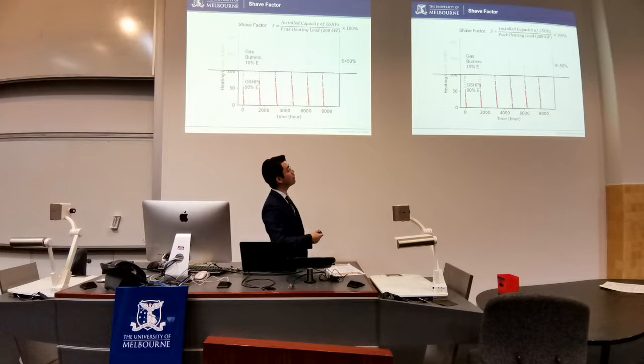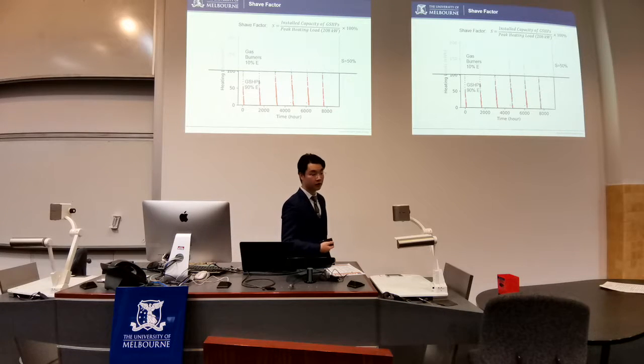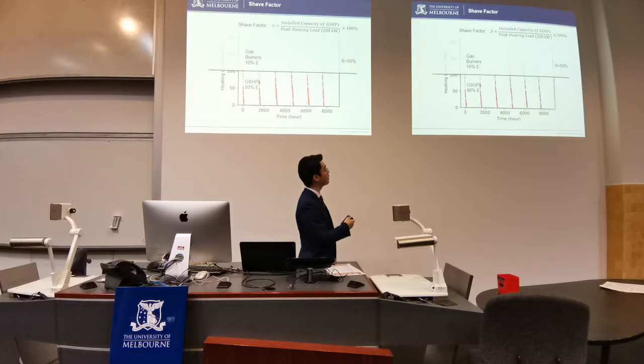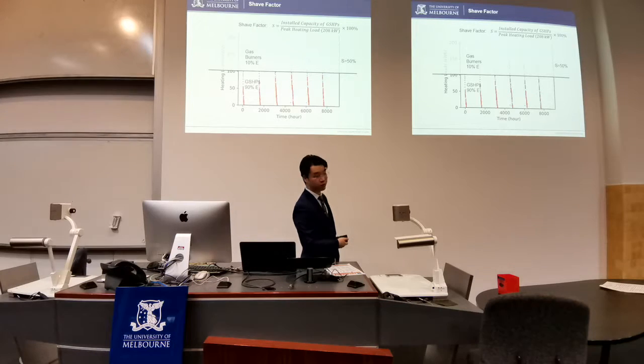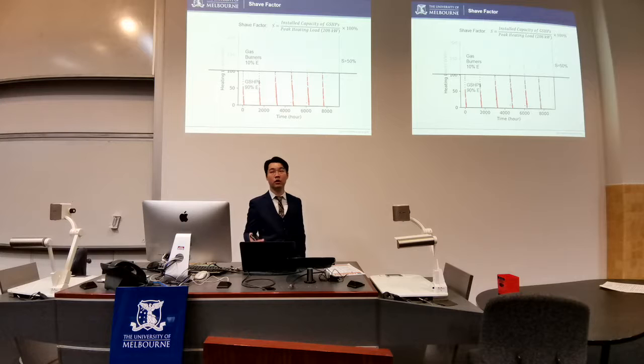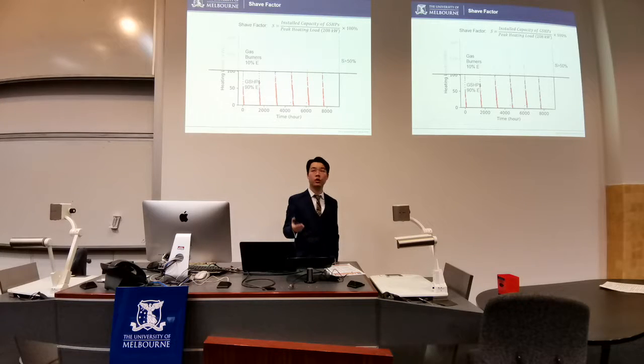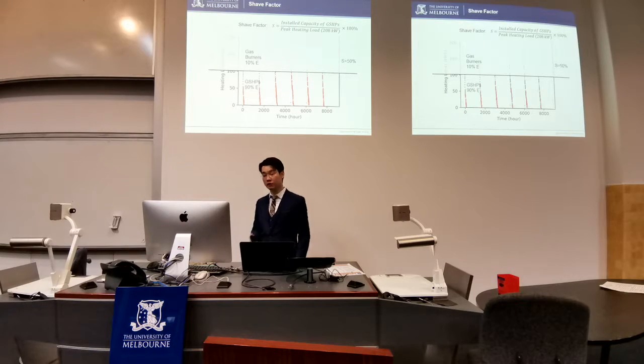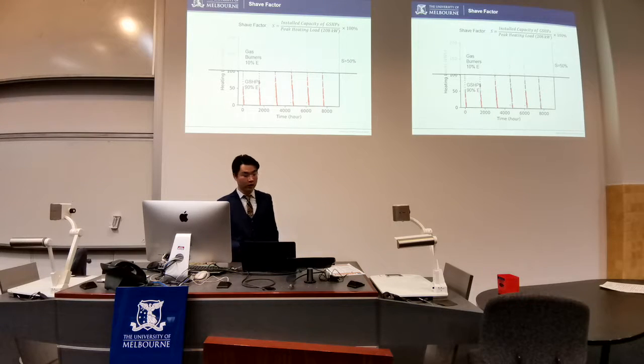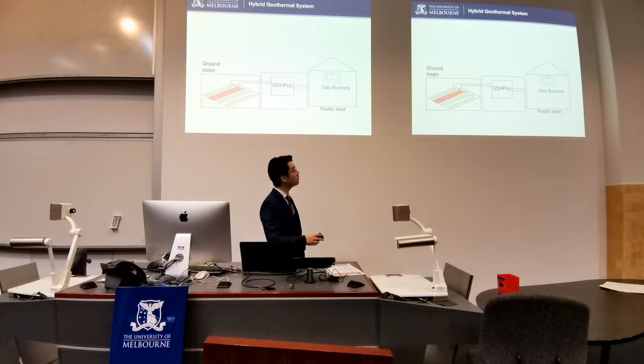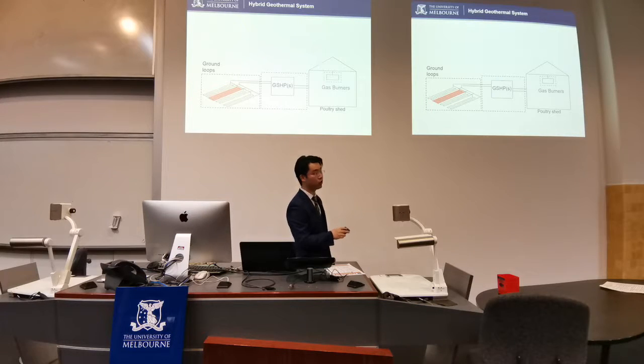Say we have a shave factor of 50%, meaning that we're installing a ground source heat pump capacity of about 100 kilowatts. In that case, only 50% of the peak load of the ground source heat pumps can still provide over 90% of the energy, while the rest of the energy can be supplied by the gas burners. Why we're doing that is because, as you've seen before, by using ground source heat pumps we're going to do quite a lot of field work, which has quite a lot of capital investment cost, while gas burners are very economical to install. And by doing this, we can form a hybrid system where we have ground source heat pumps connected to different ground loops, and we have gas burners in the poultry shed to top it up.